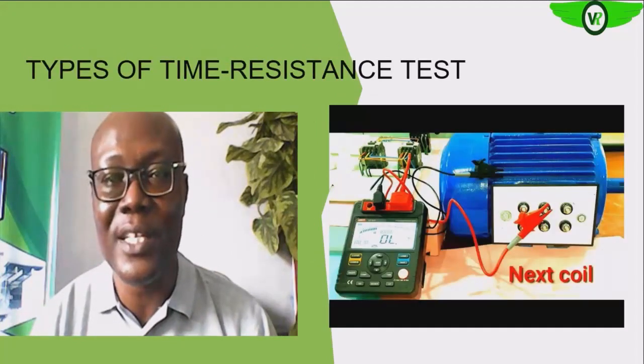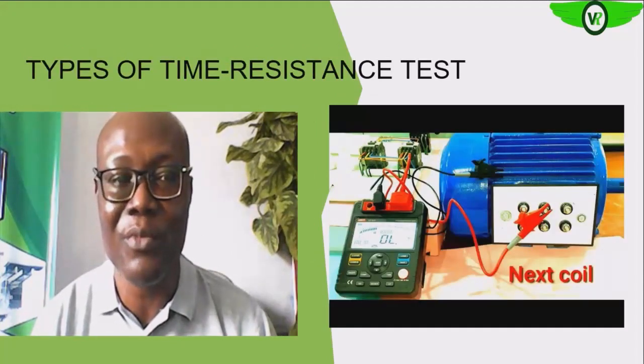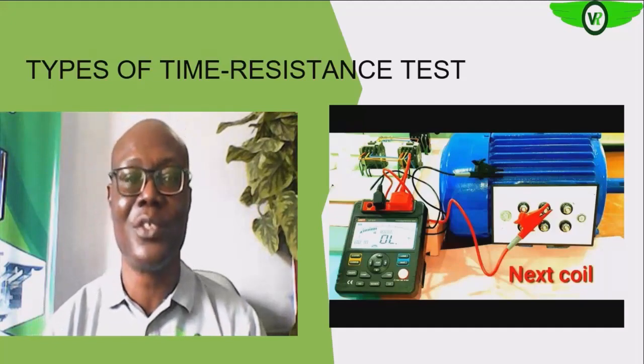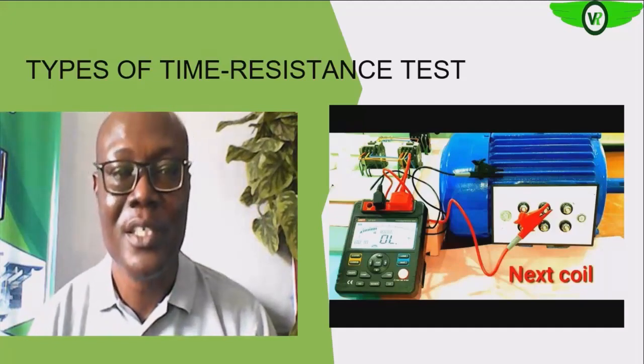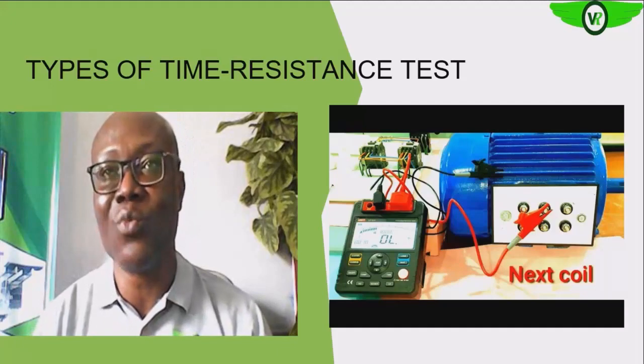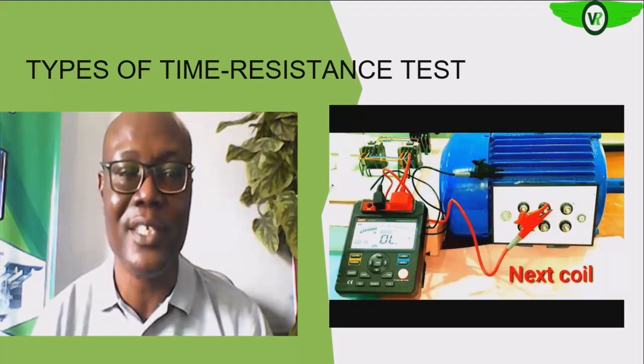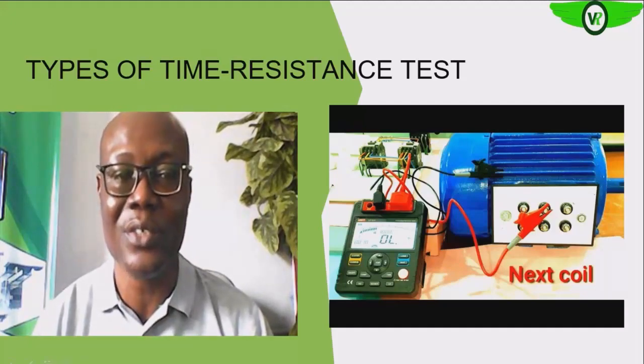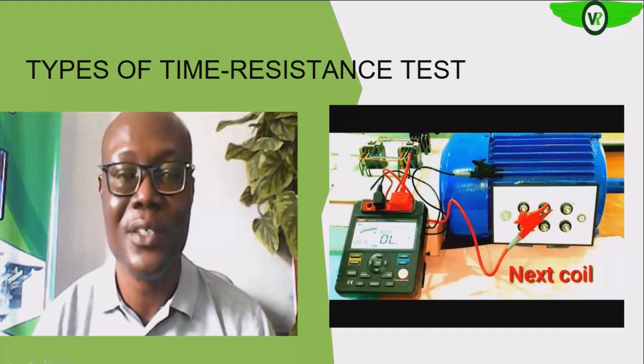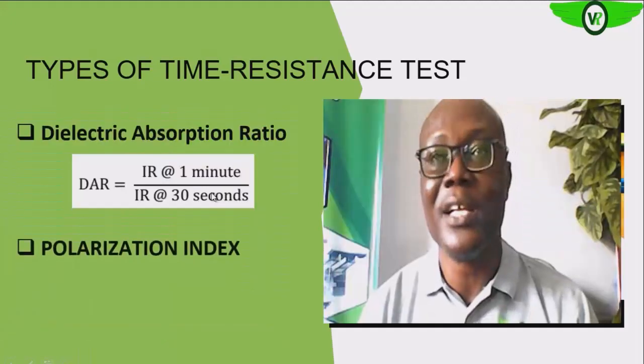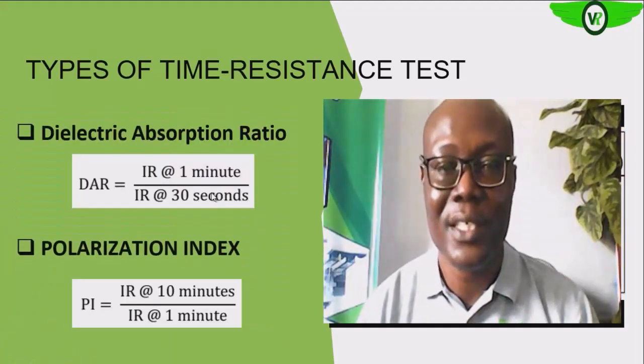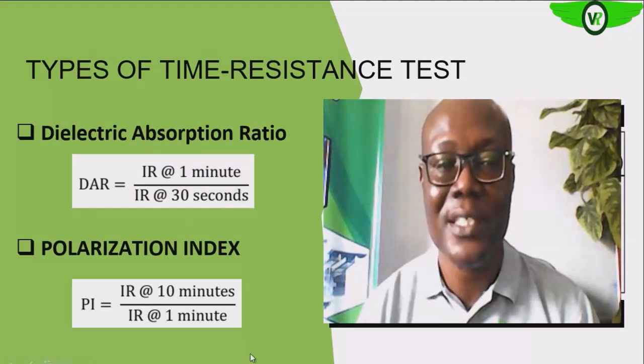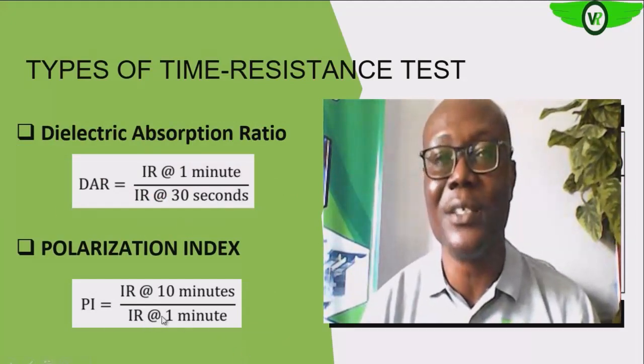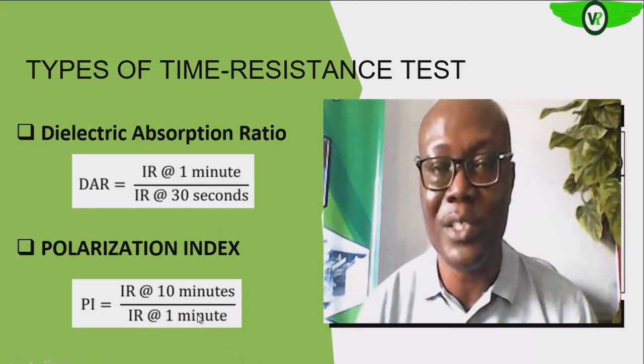The types of time resistance tests, like we said before, we have the dielectric absorption ratio test, DAR: the IR reading at 1 minute over the IR reading at 30 seconds, as you can see on your screen. Then the polarization index test: the IR reading at 10 minutes divided by the IR reading at 1 minute.